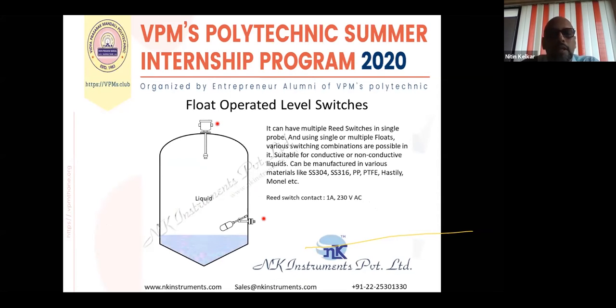See here, the side mounted level switch is operating like a cantilever. When the liquid level reaches the float, it will start floating on the liquid, and it will move. At the back end of the float, if you see, there is one rod, a tail. It has a magnet in it, and this magnet will operate a reed switch, which is inside this horizontal pipe.